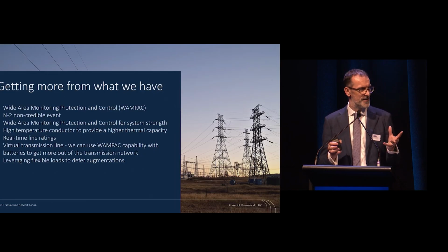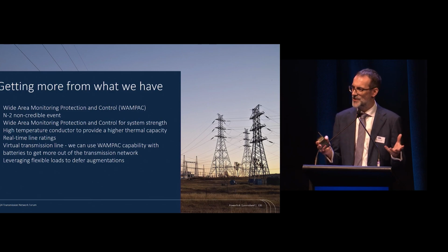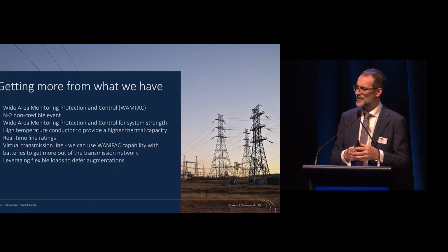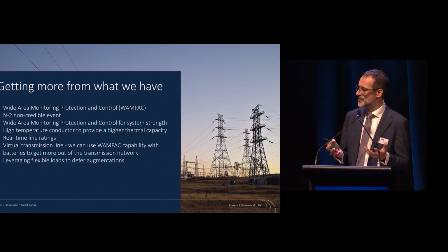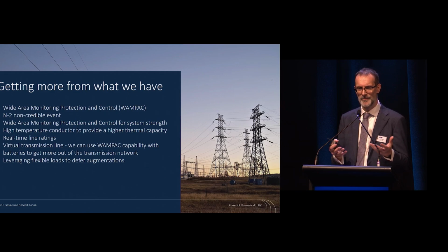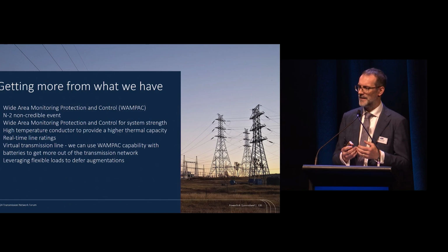A couple of them are in wide area monitoring, protection and control. We've already got it in place for one of the cut sets for a double circuit outage, to make sure that if we do end up with a double circuit outage - don't happen very often, but if they do - then we'll be able to catch the network within less than 200 milliseconds, keep it stable, and allow us to continue running.